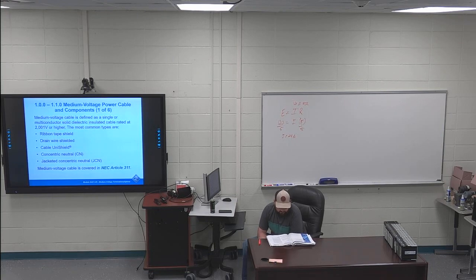My first highlight is the first sentence on the page. Medium voltage cable covered in NEC Article 311 is defined as a single or multi-conductor solid dielectric insulated cable rated at 2001 volts all the way up to 35,000 volts. So the NEC is saying the medium voltage cable is between 2 and 35,000 volts.